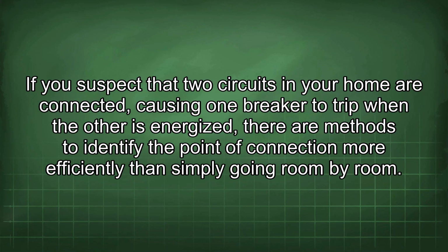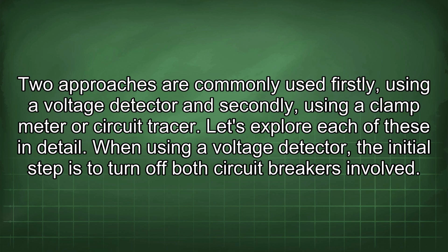If you suspect that two circuits in your home are connected, causing one breaker to trip when the other is energized, there are methods to identify the point of connection more efficiently than simply going room by room. Two approaches are commonly used: firstly, using a voltage detector, and secondly, using a clamp meter or circuit tracer. Let's explore each of these in detail.